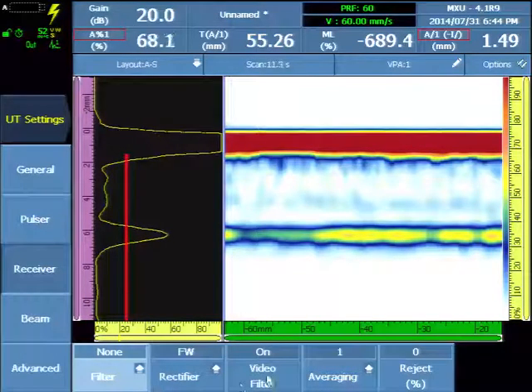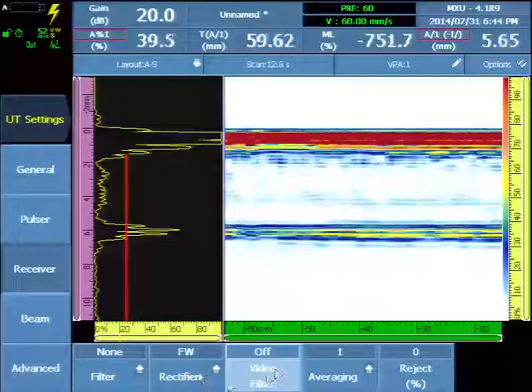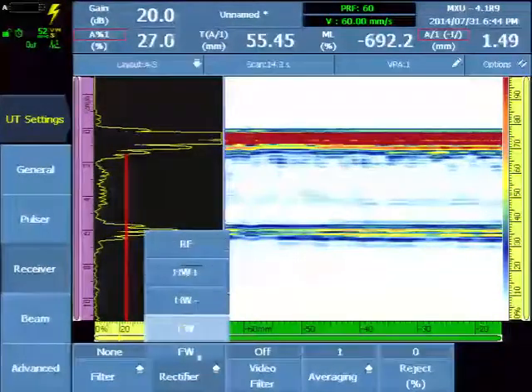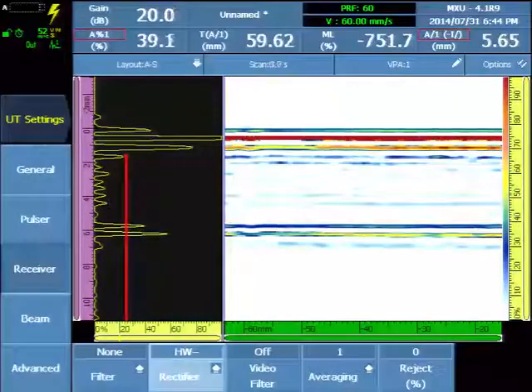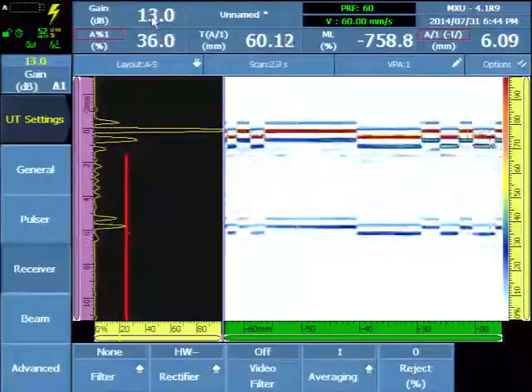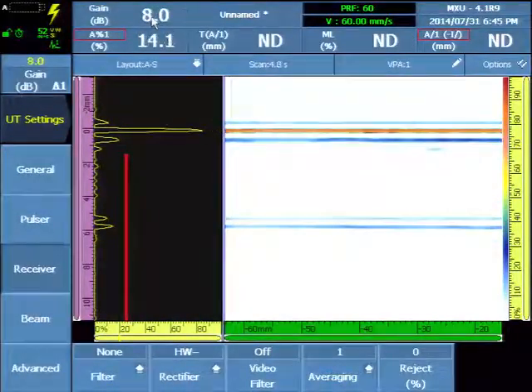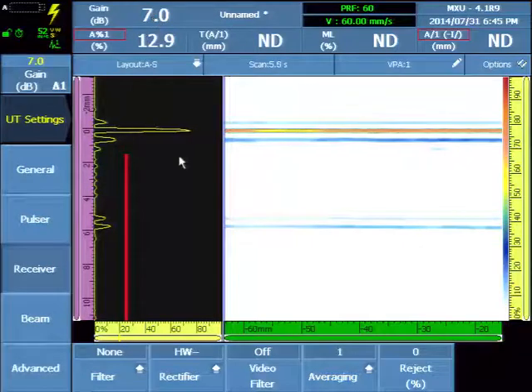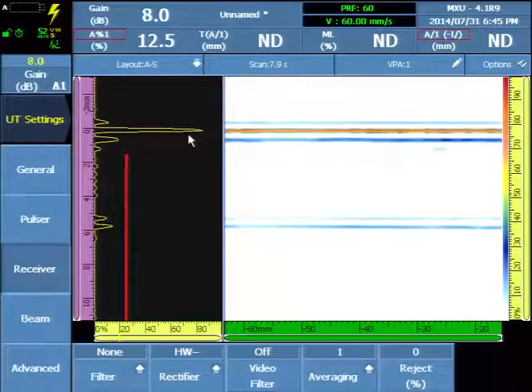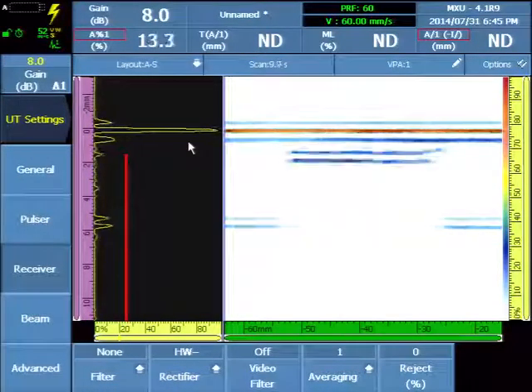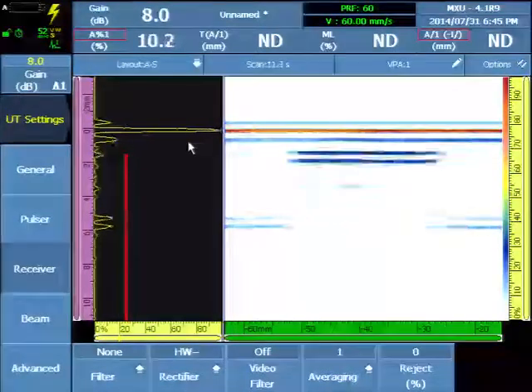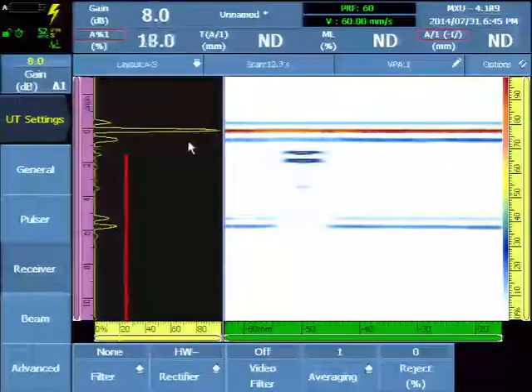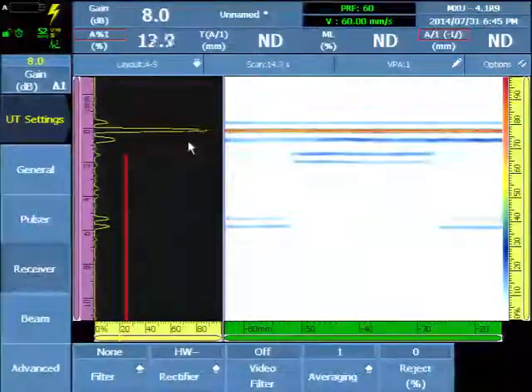For the receiver we're going to turn off the video filter. Select half wave rectified negative and reduce the amplitude until the interface signal is approximately 75 to 100% amplitude. And as I move the wheel probe I see it's stable and flat.